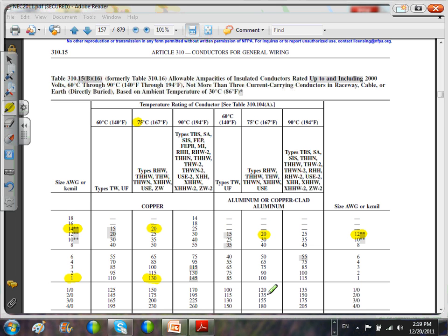And the other one, look at this one. For the 125, I need to go all the way up to here, and that will give me 2 aught. From number 1 into 2 aught if you go to aluminum. And we all know the advantage of aluminum is the weight. The weight is really cool and it's cheap. The disadvantage, of course, is you need bigger conductors, and they're not as safe as copper in terms of short circuit. They melt. The melting point is lower than copper. Any questions about this table? This is a must know for motors, for anything else. So that's the table that we use.